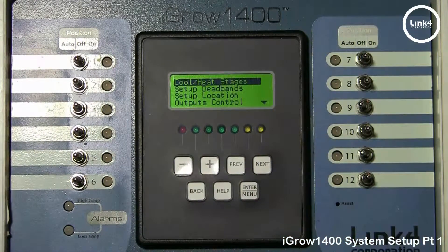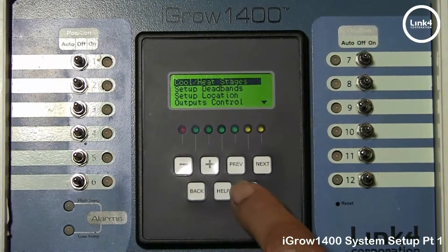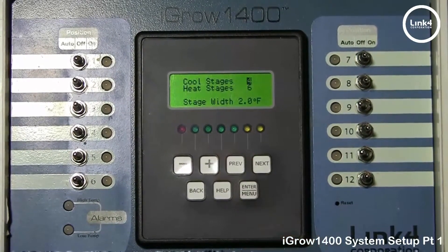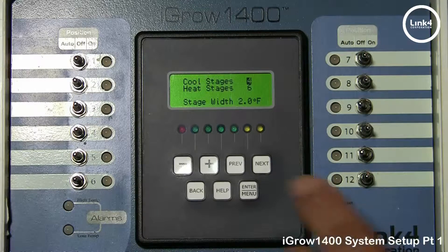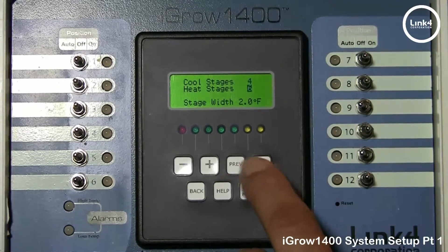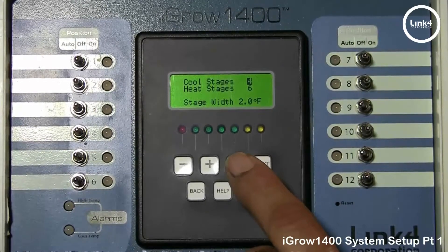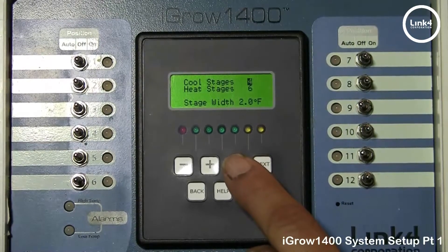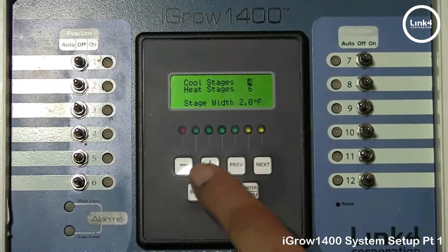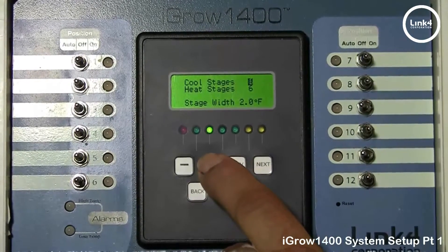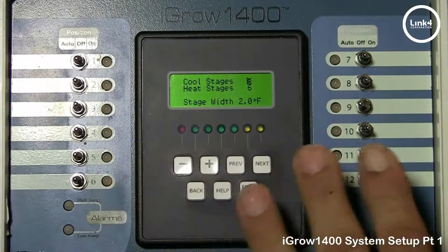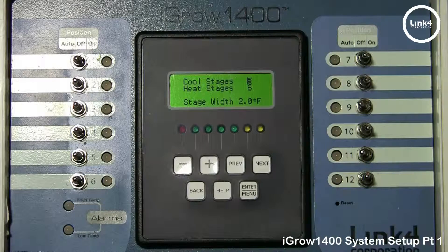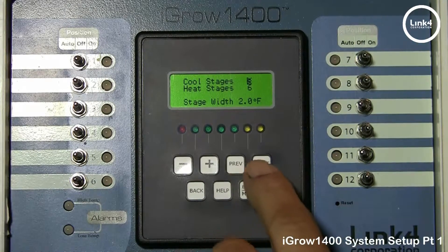The first item on the list is Cool Heat Stages. The Cool Heat Stages screen allows you to select the amount of cooling and heating stages that you intend to use. Hitting Previous or Next rotates between the cool stages and heat stages. For example, if you choose three cooling stages, then throughout the remainder of the programming only three cooling stages will be displayed.